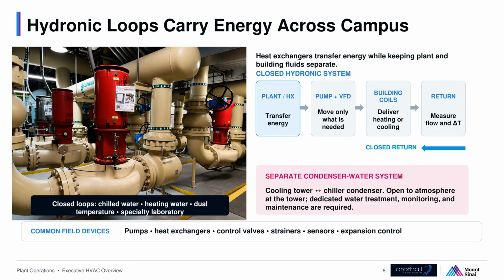Condenser water is different. It is a separate recirculating system that is open to the atmosphere at the cooling tower. Because evaporation concentrates dissolved solids and the tower is exposed to air, that loop requires dedicated water treatment, blowdown control, monitoring, and maintenance. In every loop, poor delta T, a restricted strainer, a drifting sensor, or an incorrect valve position can increase energy use without improving room conditions.